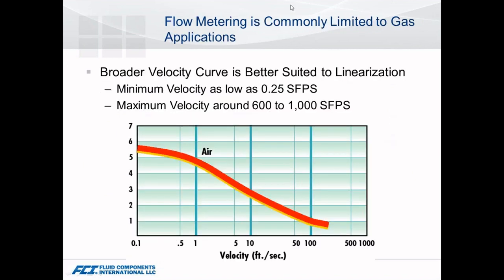When you look at gas compared to a liquid, the previous slides showed liquid limited to about five feet per second as a maximum velocity. With gases, that smaller cooling effect due to thermal conductivity allows us to get ranges much higher — roughly 200 actual feet per second, equating to calibrations in the 600 to 1,000 range. One area that really benefits from thermal is being able to go very low in flow — that quarter foot per second is barely moving flow.